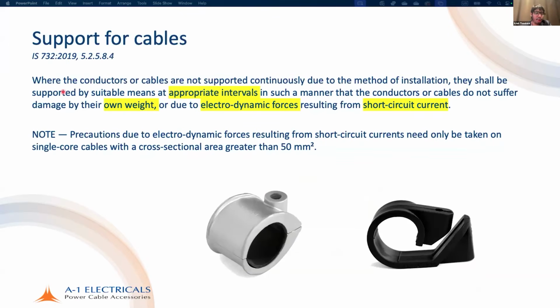Cables are to be supported, and so where conductors or cables are not supported continuously due to the method of installation, for example, a method of installation where it is continuously supported may be a tray, but in the case of a tray, they have to be secured. They shall be supported by suitable means at appropriate intervals. Now, the crucial thing is these conductors and the cables should not suffer damage by their own weight or due to electrodynamic forces resulting from short circuit.